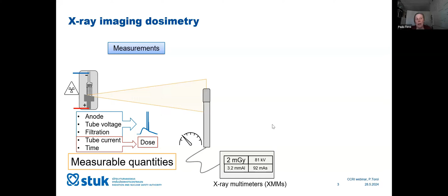One challenge in this field is that we do calibrations in specific calibration setups with reference radiation qualities. When we do the measurements in clinical practice, the spectra change quite a lot because we want to have good image quality. So the optimization is done by changing the tube voltage and the filtration to get the best possible image quality for the patient. And we cannot really cover all these situations in the calibration practice. So to keep the traceability, we need an unbroken chain of measurements with uncertainty estimations. We have to be able to understand how this change in conditions will impact our result and our uncertainty.